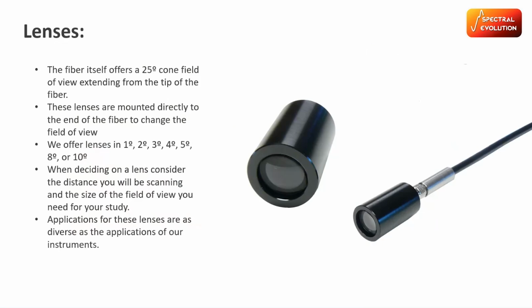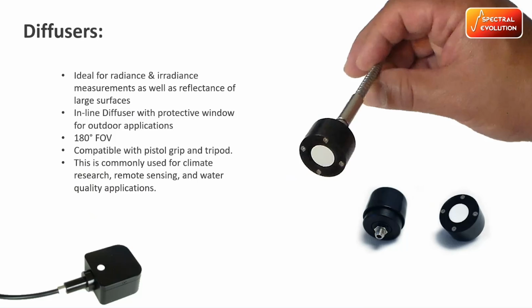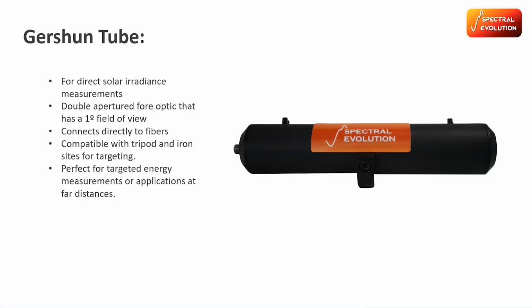And as I iterated earlier, we have several different lenses that can be used to accompany the Sensaprobe. We have 1, 2, 3, 4, 5, 8, and 10 degree lenses. And then the bare fiber has a 25-degree field of view. And so by doing that, you can ensure that when you're sampling things that are far away or closer, you can manipulate that field of view and make sure that you're sampling at an area that is relevant to your study. And then we have diffusers that give you a 180-degree field of view and work the same way as the lenses. And all of these lenses and diffusers can be radiometrically calibrated as well. And then here we have a Gershun tube for 1-degree field of view measurements and measurements of energy sources.